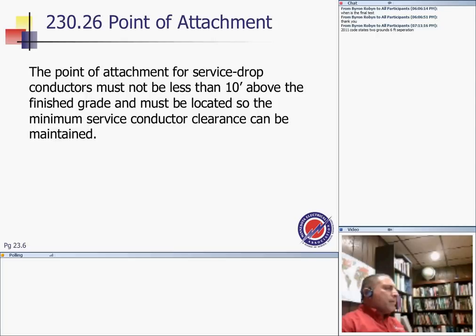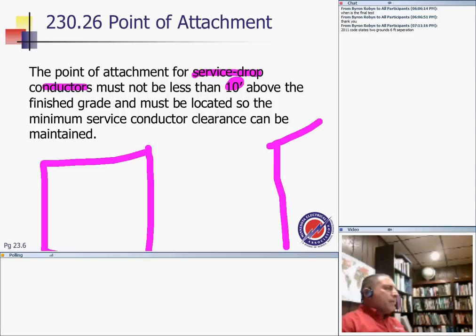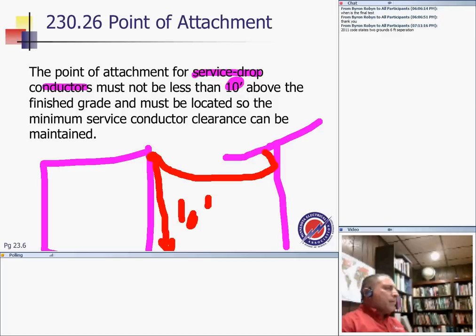Point of attachment. The point of attachment for the service drop conductors must not be less than 10 feet, as we all know, guys. Power lines are coming in here to your building, and here's my power lines, and you come over here, bringing it from the power lines all the way up to the point of attachment. You have to maintain 10 feet. And there is a restriction on how high you can go. The point of attachment must be at least 10 feet above the finished grade, and must be located so that the minimum service conductor clearances can be maintained.